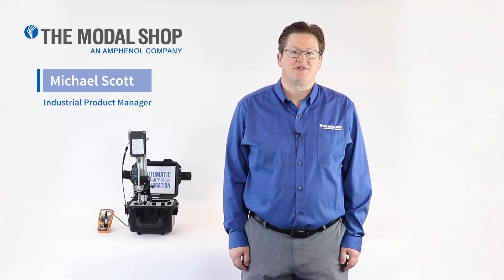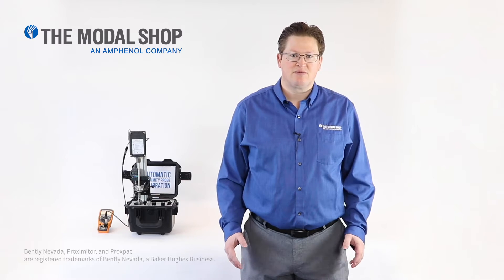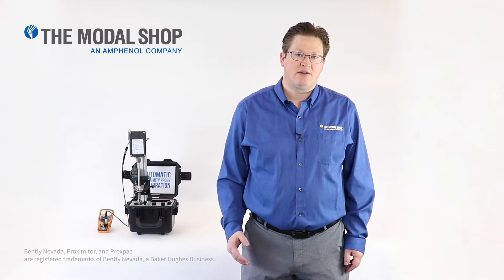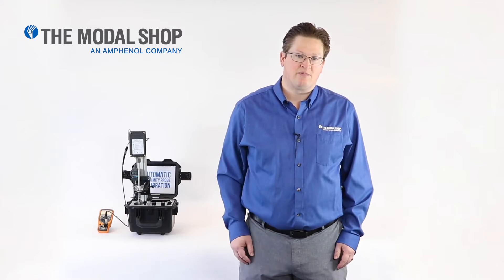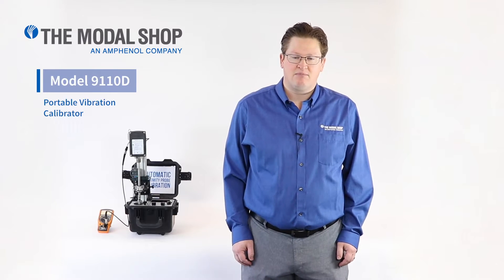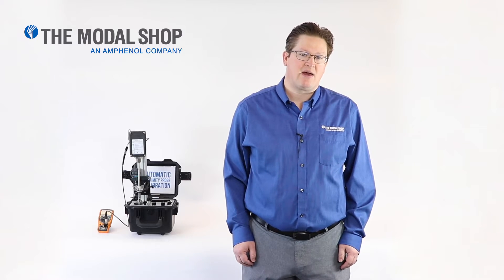Hi, my name is Mike Scott, Industrial Product Manager for the Modal Shop. In today's video, I'm going to show you how to test a Bently Nevada Proxpac. A Proxpac is a reverse mount proximity probe installed inside the end of a long probe housing or holder. At the top of the housing, there is an enclosure for the electronics — the Bently Nevada Proximitor. Other OEMs also make this type of equipment. I'm going to test it with a Model 9110 Portable Vibration Calibrator that will show the sensitivity of the proximity probe during a dynamic test.